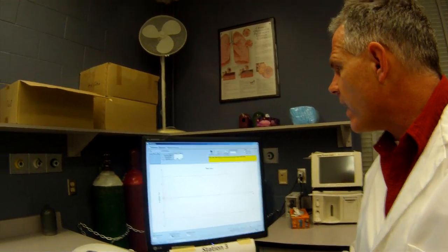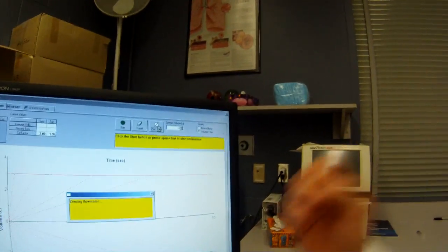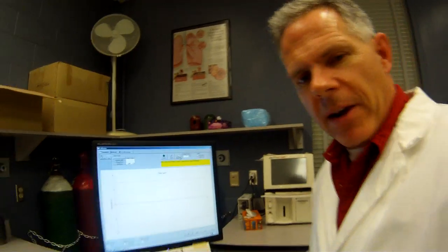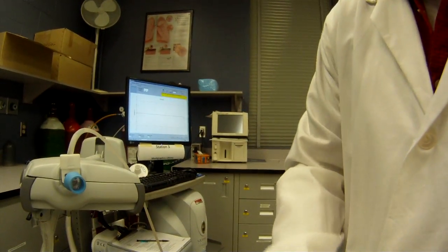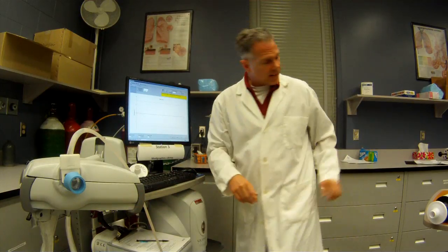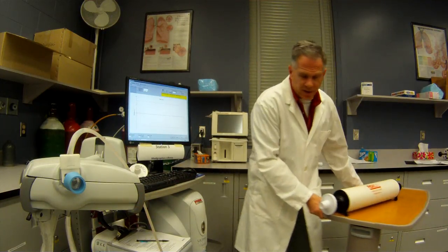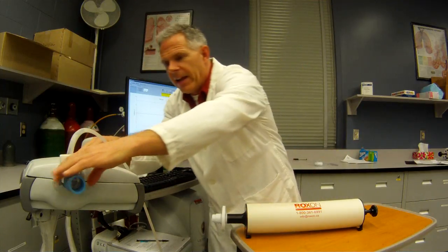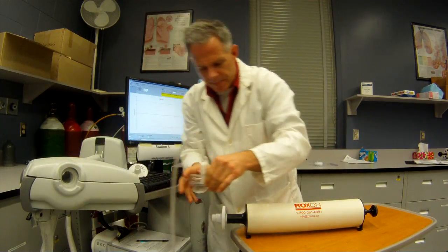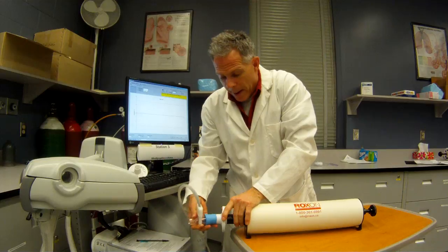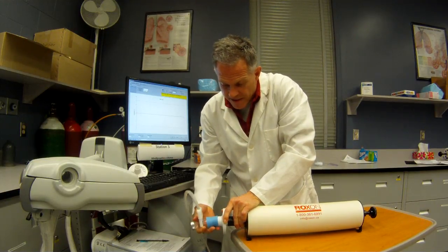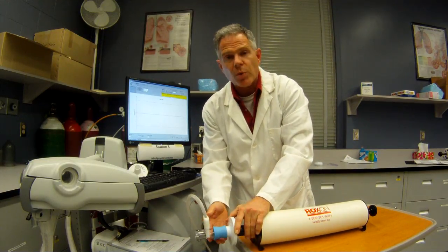Next thing I do is I like to zero the pneumotach. It's really important that it be zeroed. Don't hit the reset unless you've got a very specific reason, and I'll talk about that probably during lecture of the lab times. All right, so I'm going to set you over here like this. So we're going to be calibrating this pneumotach. So I need a 3-liter syringe. And I'm going to just take this off of here. So this can be done anywhere. We're going to do this every single day before the device is used.